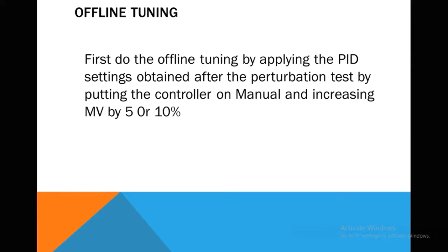So you have to have an initial setting done, for which you require maybe a test by the Ziegler-Nichols method, which is giving a perturbation or a change in the set point by at least 5 to 10% of the MV value, and then watch the response, collect the data and analyze to yield the proportional, integral and derivative settings. This is slightly cumbersome, and without any data collection software this will never work. So we will go by some other method.